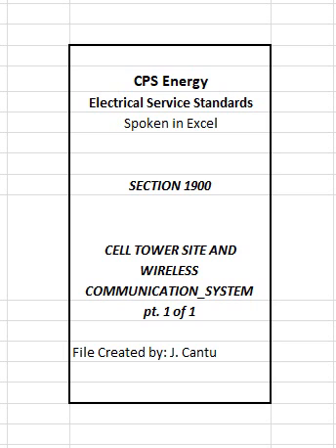Note: customer will be required to furnish and install a step-bus auxiliary gutter where service lateral conductors or any one set of service entrance conductors are sized larger than two 350 kcm conductors per phase. B. Modular metering equipment. Service may be designed with minimum 600 ampere rated modular metering equipment. Modular metering equipment shall be capable of supplying 6 meter positions. Where more than 6 meters are anticipated, a main disconnect shall be incorporated into the design of the modular metering equipment, refer to figure 1812.